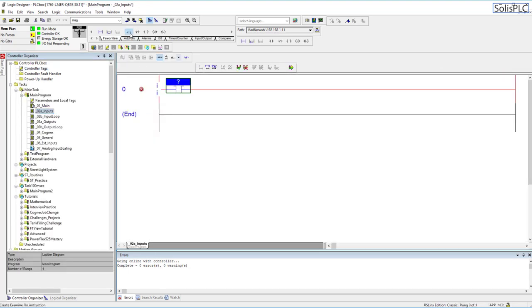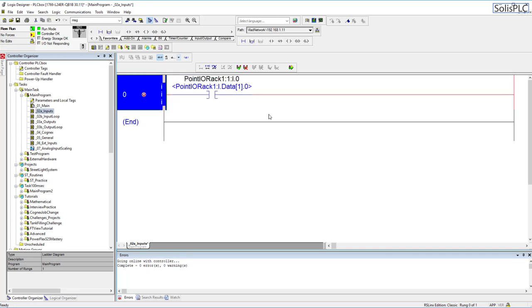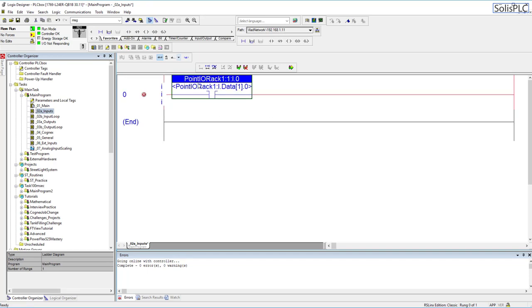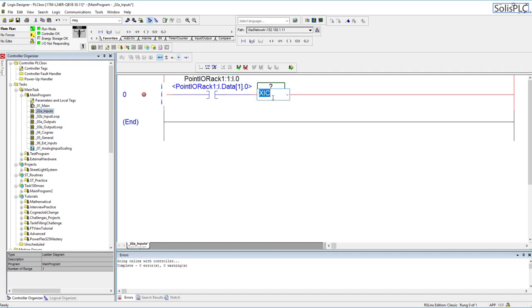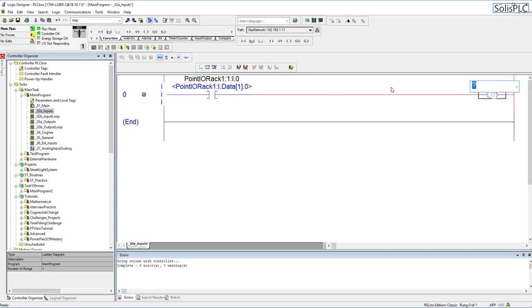Going back to the routine, all I'm going to do is create a very simple structure which is going to essentially take the tag on the input side and then store it in a local boolean. The reason why this is done is so that in case something happens to this input, you need to move the wire or anything else just fails on the hardware, you can really easily reassign different inputs to your local tags. That just makes it really easy to work with.